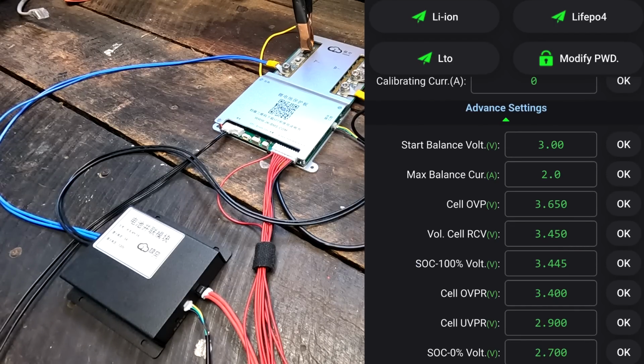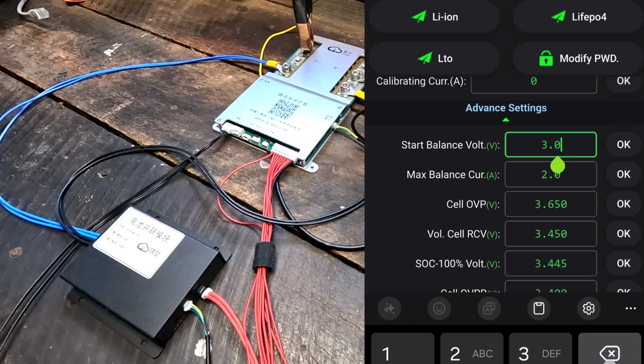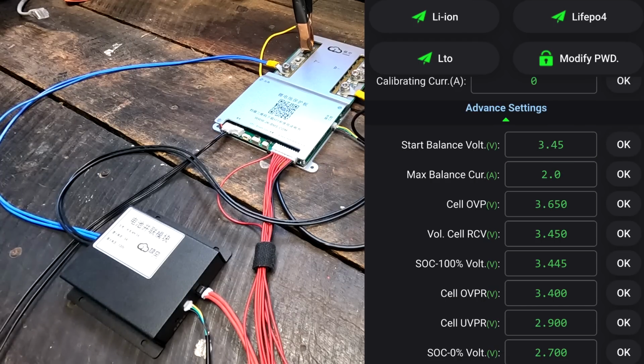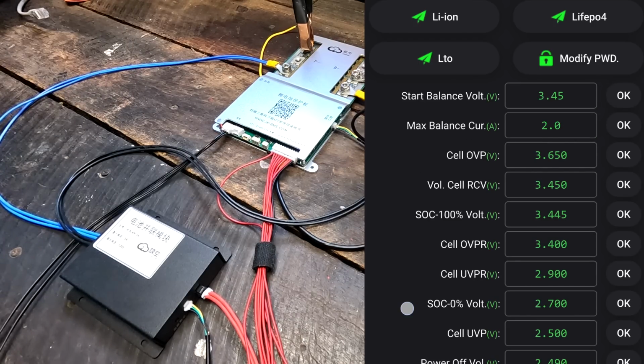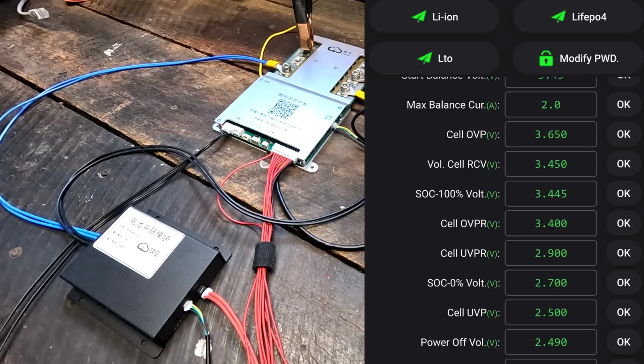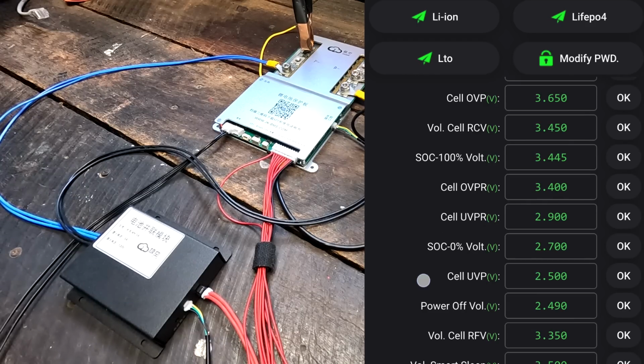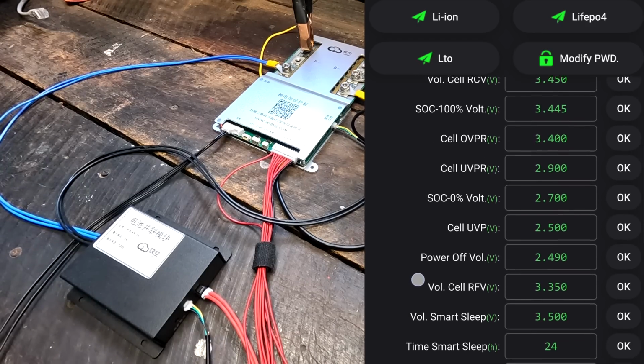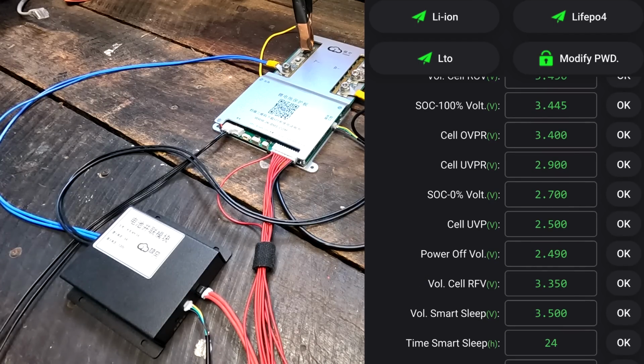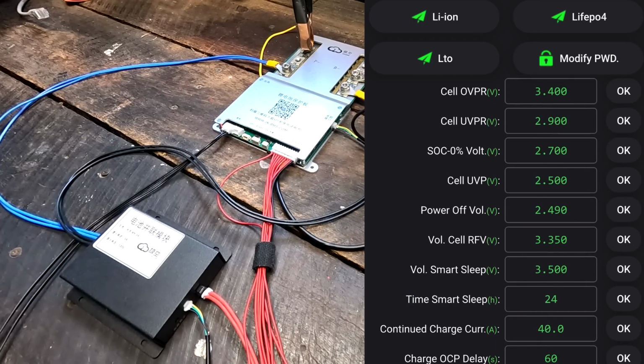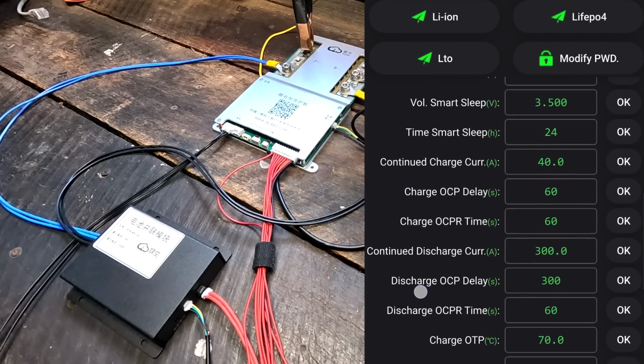Start balance voltage at 3 volts is too early, it needs to be at least 3.45 to 3.65. 3.4 is the requested charge voltage from the inverter. State of charge resets at 3.445, perfect. Recovery state of charge 0 voltage at 2.7. Undervoltage protection 2.5, power off at 2.49 volts. Nice, and we've got a requested float voltage of 3.35 per cell. Perfect, that looks all good. I'm impressed.